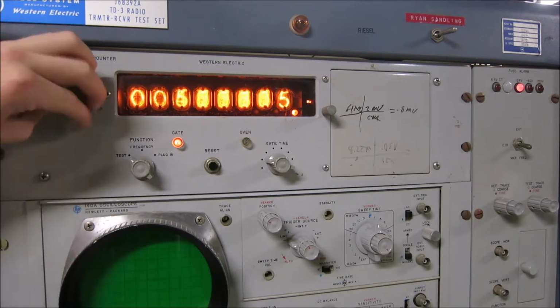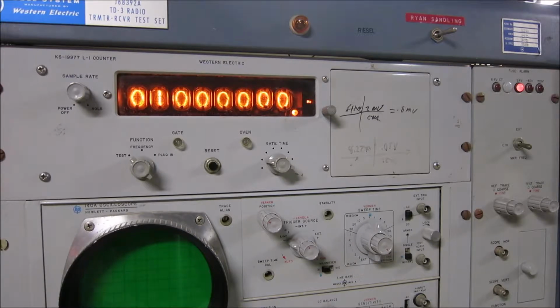Now if I put it on hold, it'll take the frequency that we've tested and hold it, and it won't increase any further. Now if I set the unit here to the highest frequency possible, you'll notice that it will count up, and then it should hold that frequency if operating correctly.